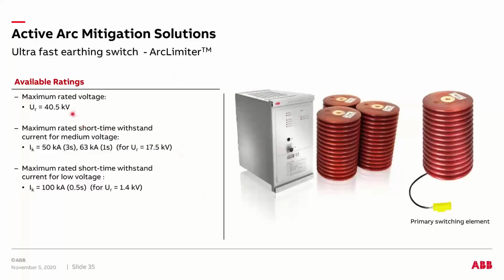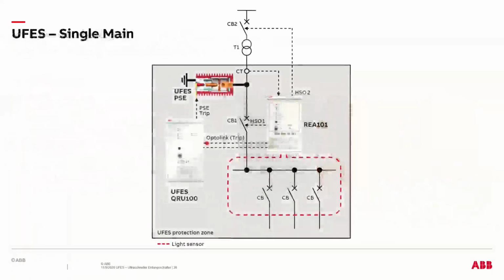So this particular equipment is medium voltage rated up to 40.5 kV, but it can also be used for low voltage applications as well. For low voltage applications, it is rated up to 100 kA, and for medium voltage applications, it is rated for up to 63 kA for 1 second and 50 kA for about 3 seconds. So it's a pretty robust device that can be used for either low voltage or medium voltage applications.